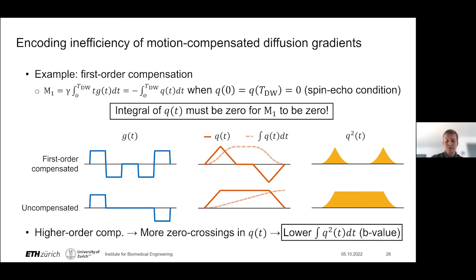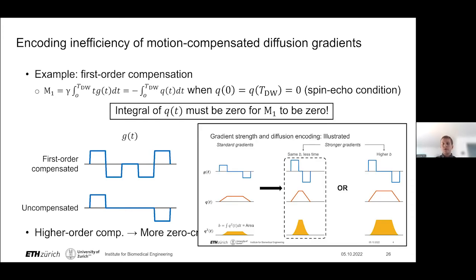This disadvantage becomes even worse as we increase the order of motion compensation, because more zero crossings will be required in q(t) as we must null higher-order integrals, resulting in a lower b-value. By using strong gradients, we address this using the first method mentioned: aiming for a certain b-value and doing so in less time. Achieving a b-value of 1000 with first- or second-order compensation would result in too long an echo time on a standard system, but doing so with stronger gradients suddenly becomes much more feasible.